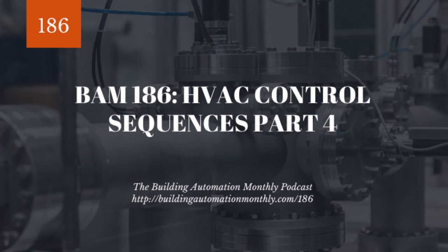supply flow. And what we would typically have interlocked with these units, especially if we have variable return air boxes, is an exhaust fan interlocked, not part of the unit, but interlocked with the operation of the unit. And that's how we're going to make sure that we are varying our exhaust to either do our volumetric offset or just to maintain positive pressure. Most times we're going to be looking at space pressure and maintaining that. Sometimes we'll do it through a volumetric offset. Most of the time, like I said, we'll have a TSI monitor that will measure pressure outside the space and inside the space, and will maintain a positive pressure scenario. All right. So that's fan speed control and pressure control.